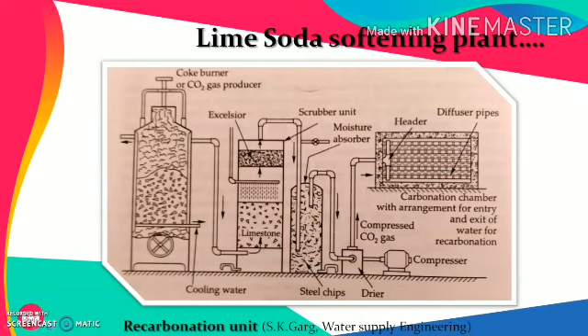This is the figure of a lime soda softening plant, where all units essential for recarbonation have been shown. This includes the coke burner, where the carbon dioxide is actually produced. Then it passes through the scrubber unit, where all other impurities are scrubbed or removed, after which it passes through the moisture absorber, and the pure carbon dioxide gas, in the form of a compressed gas, is supplied to the softened water. For this, generally diffuser pipes are used.